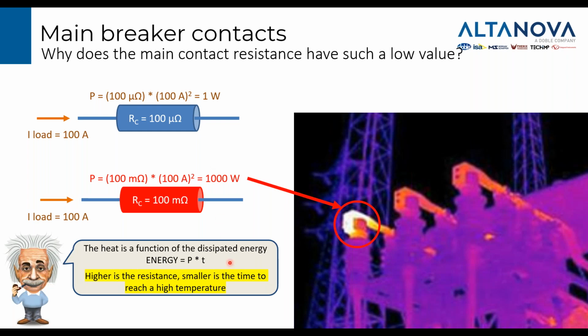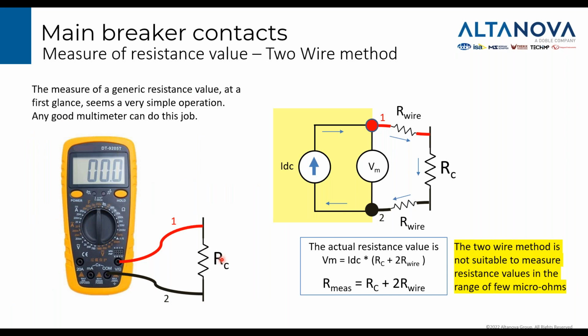You have to remember that heat is a function of the dissipated energy, not just power. So it depends very much on how long this situation lasts. I can have a very high power, but if it is dissipated for a very short time, it will not be a big issue. Vice versa, if you keep this condition for a long time, it will be an issue. But how to test in a reliable way a very small value of resistance?